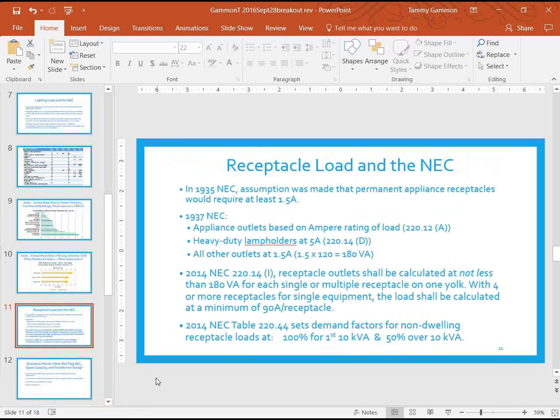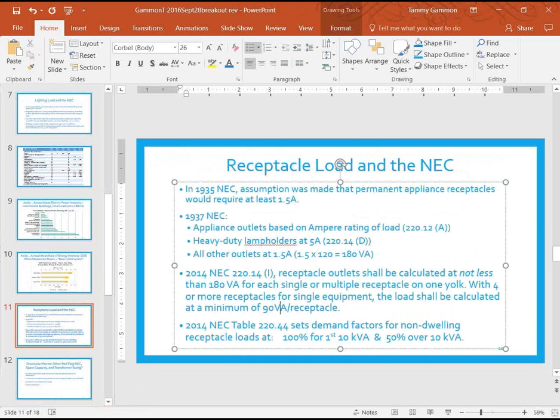So if we look at the 2014 NEC, and the reason I say 2014 is because I have a 2014 NEC sitting right here, and I don't have a 2017, but I'm sure the 2017 is most likely the same. Receptacle outlets shall be calculated at not less than 180 VA for single or multiple receptacles on one yoke. And that basically, if you have 4 or more receptacles on a single piece of equipment, the load should be calculated at, that I put like 90 amps. That is totally wrong. I'm sorry. I meant to say 90 VA per receptacle.